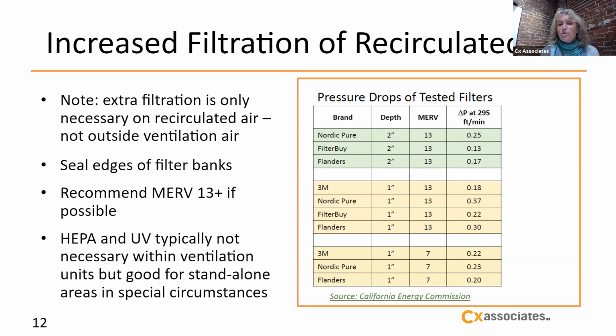Some people have recommended putting HEPA filters or UV light in a ventilation system. We are not recommending that because the maintenance on a UV light is pretty intense. There are all kinds of safety precautions you need to take when handling UV. They're also very expensive, and you have to replace them. To be effective, you have to replace them every 3 to 6 months.